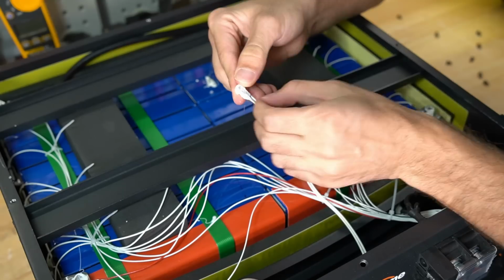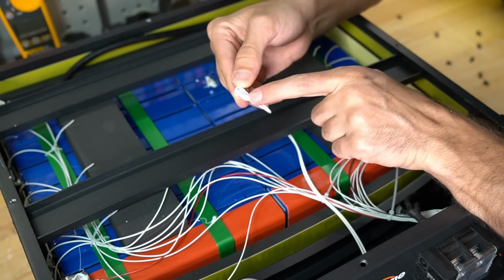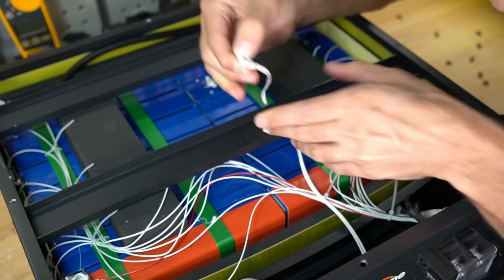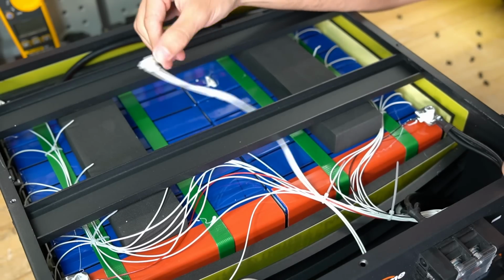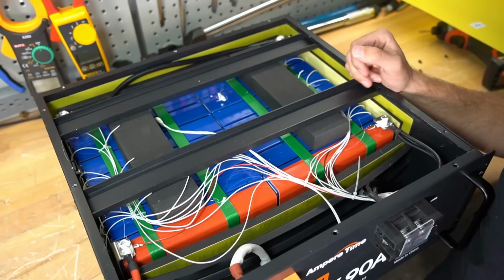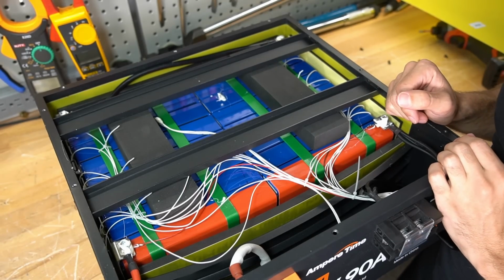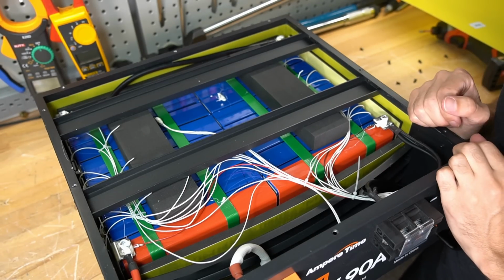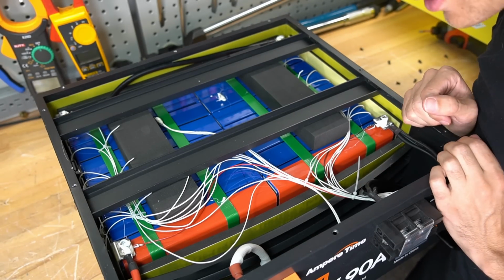No way. This is a high temperature switch, just like their cheaper model batteries. Does this not even have a temperature sensor? I do not see one. This is probably the worst build quality server rack battery we've had on the channel so far. This is atrocious compared to what we're used to.